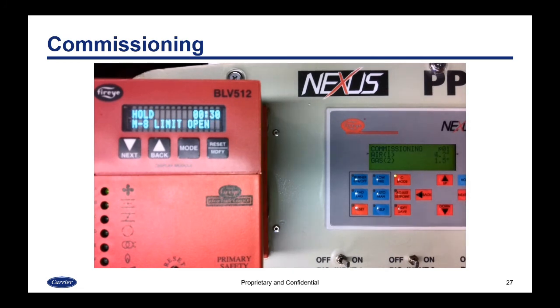So we set the standby and we hit next, and it moves to position 1, which is going to be the purge position. Now the handshaking between the two is going to wait until we move through our commissioning process. So it's not going to send any feedback or any commands until we actually set the position we want it to go to. So right now we're going to set the purge position. So it's going to be with the air damper open to, looks like 90 degrees.